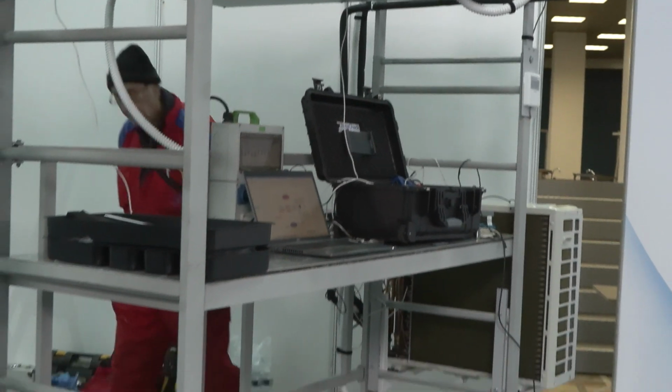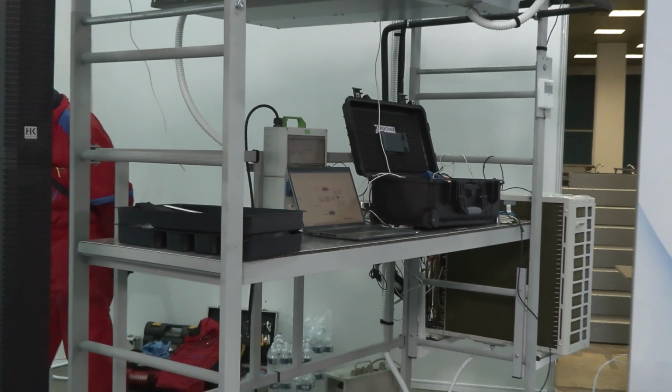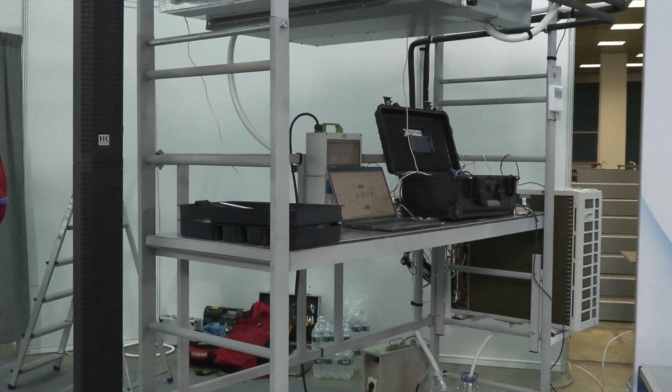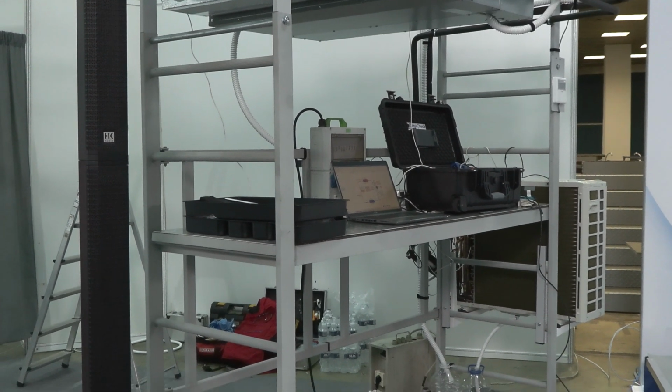This is a demonstration unit that Mr. Pekovic and his team put together for us. It's really nice. This type of system normally does not have two pressure connections directly on the compressor, so we have measured one temperature in the condenser instead of pressure.